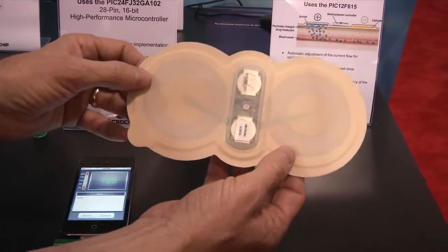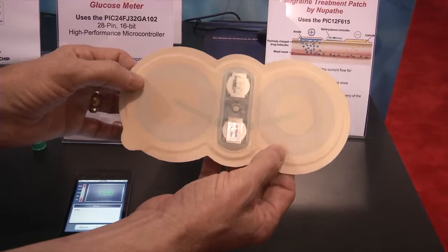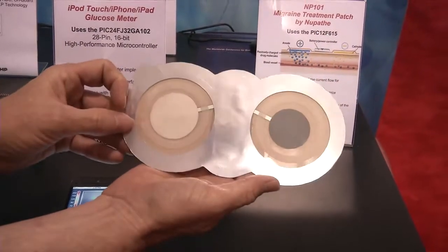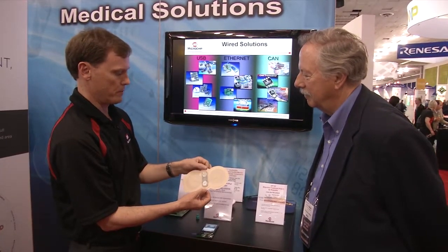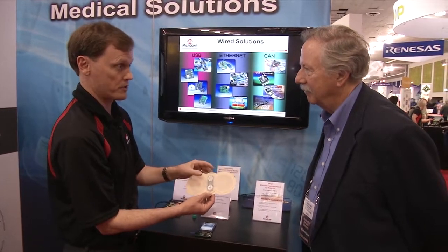The next one is a device that was actually created by one of our customers called Nupathe. This is a drug delivery system that uses a process called iontophoresis. On the backside would be patches that contain their medication. The user would peel off the backing and put it on their arm like this, and then it generates an electric field that creates a current that carries that medication through your skin, gets into your bloodstream, and goes systemic, and actually treats a migraine headache. So it gets over some of the problems that migraine sufferers have with taking pills and also giving themselves shots.